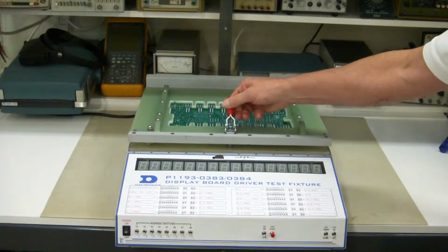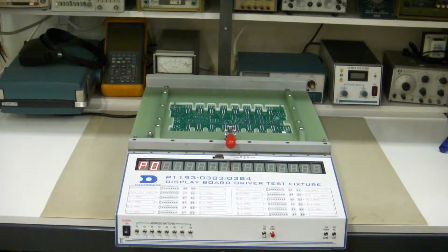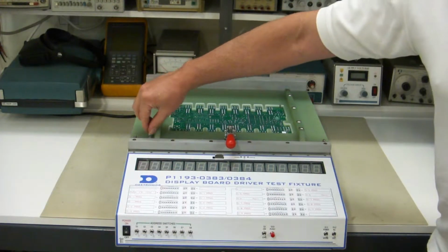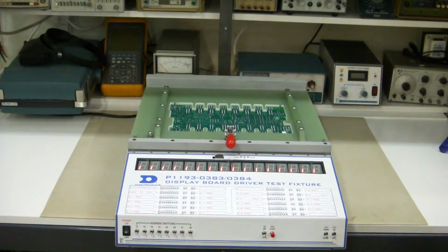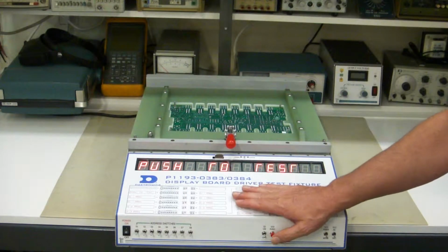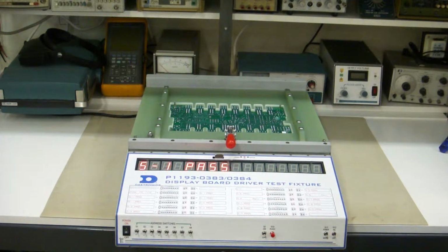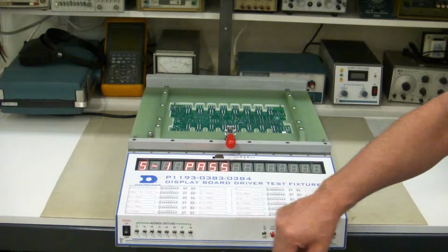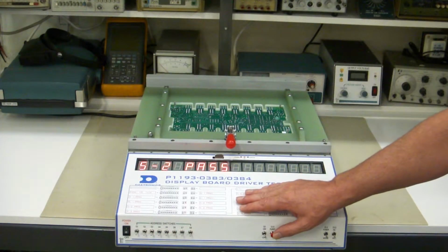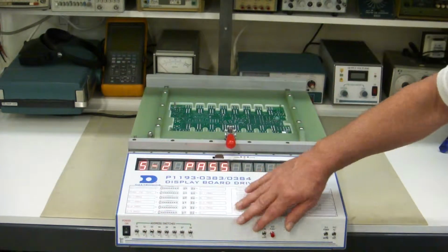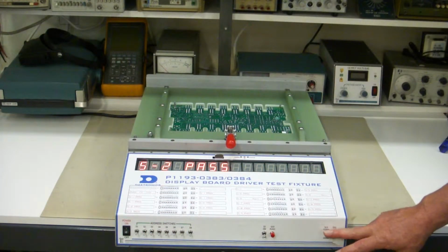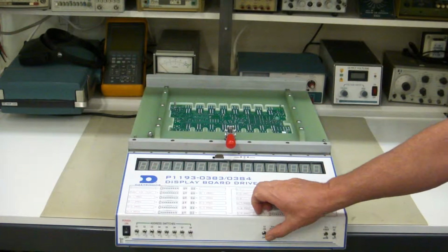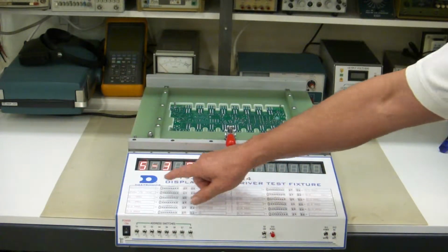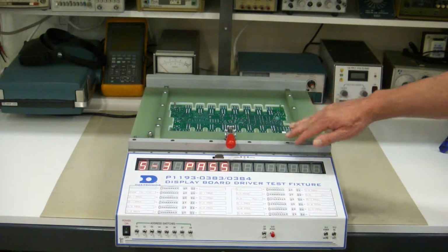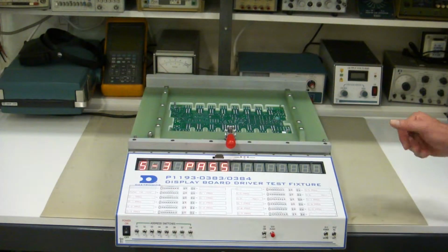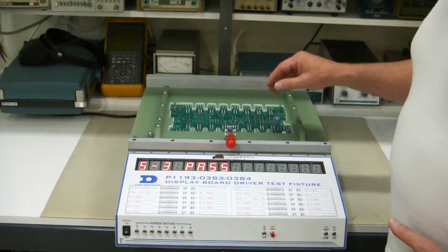To demonstrate this, we'll just lower this press plate and it will power up because it activated a switch right here with this press down rod, and it starts to cycle through its self-test. Now what we'll do is show you how you interrupt this self-test with these buttons on the front panel, and you can cycle through a few of the internal self-tests, dial up some address switches, and do all kinds of things with this front panel. This is a quick reference guide for the technician to follow in order to go through all the steps necessary to test this board. So that basically describes the functional workings of this.